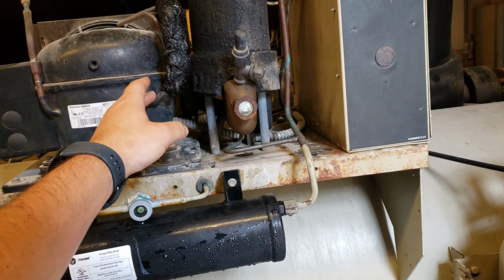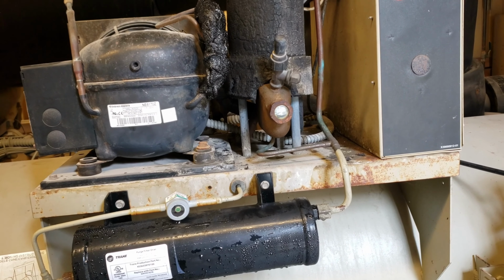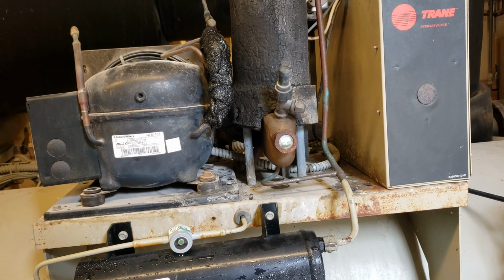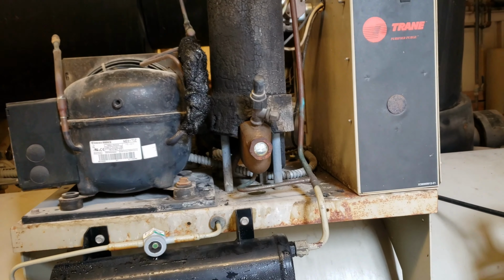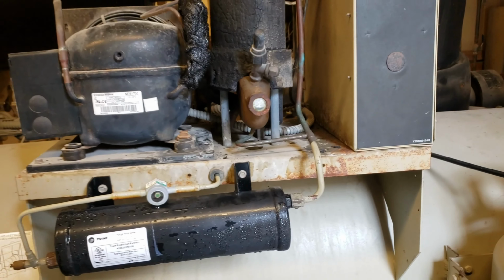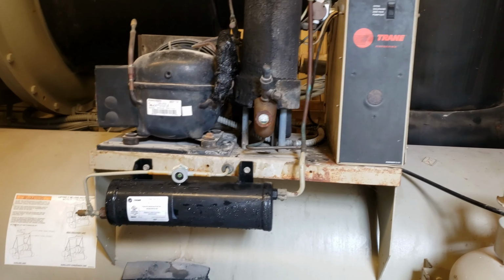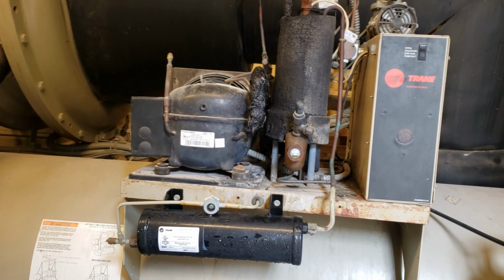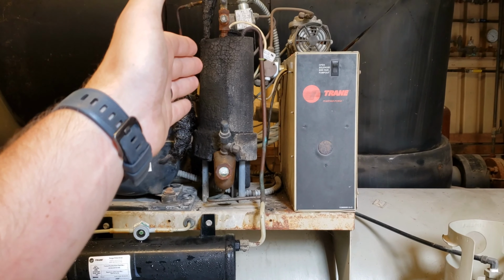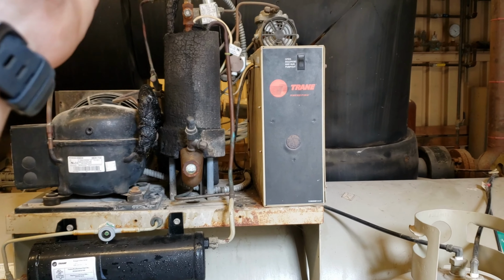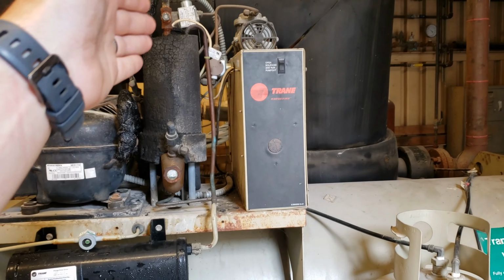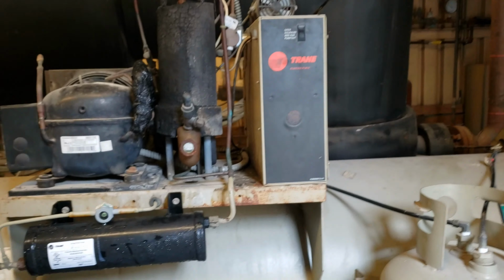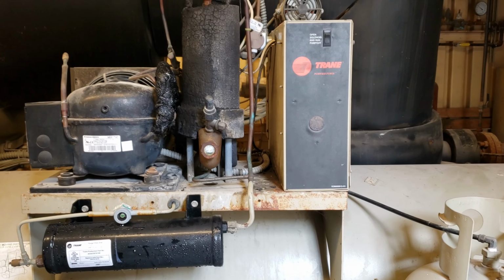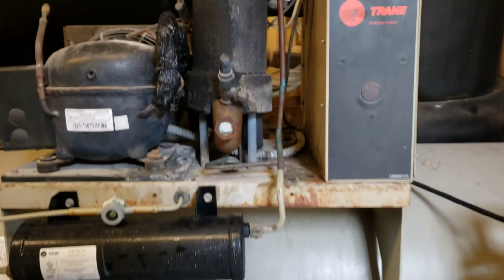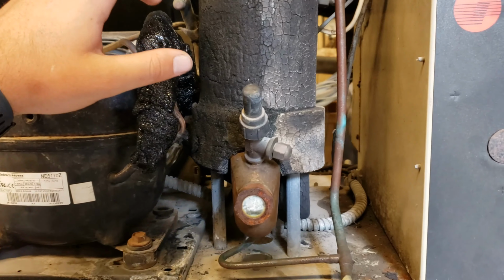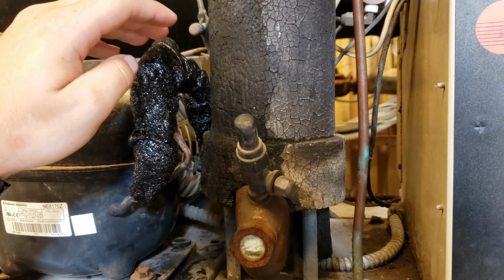It wants this suction temperature to be, I believe, between 50 to 60 degrees below the saturation or the liquid temp for the refrigerant. When it registers that, it knows that the purge assembly is full of atmosphere, and it needs to purge out on a pump out. And so anyway, it wasn't going through that cycle. It was close.